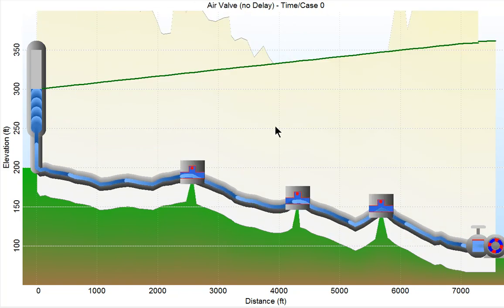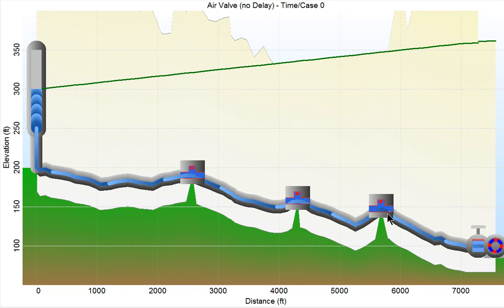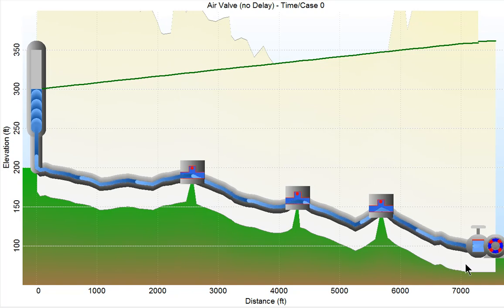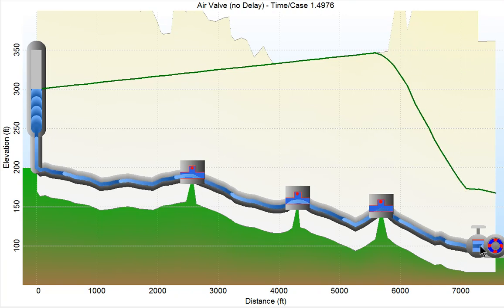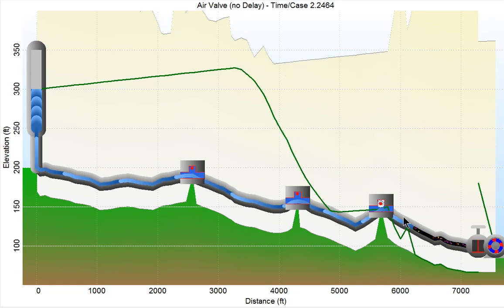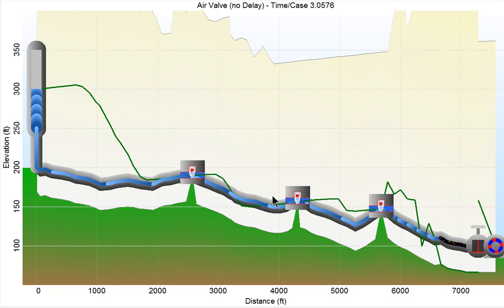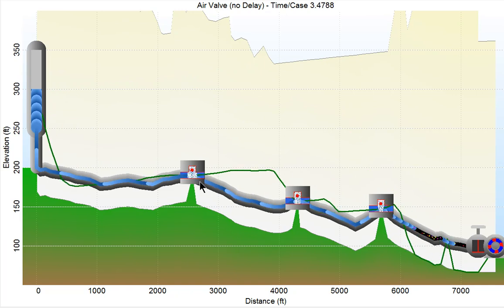Now we're going to repeat the simulation for a system with some air valves. We have three air valves positioned here at high points in the system. We're going to run the same surge analysis. The pump slows down, the check valve closes, and as you go down the line, you'll see that there's no cavitation beyond the air valves.